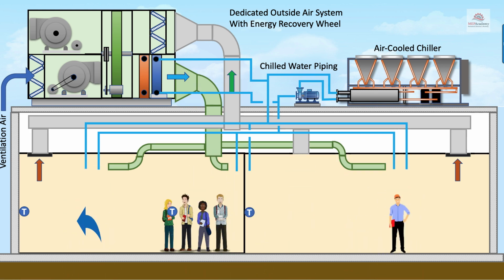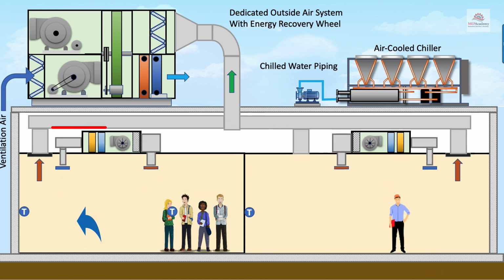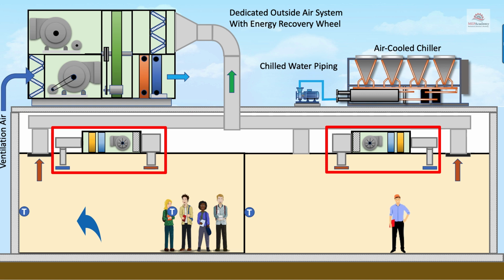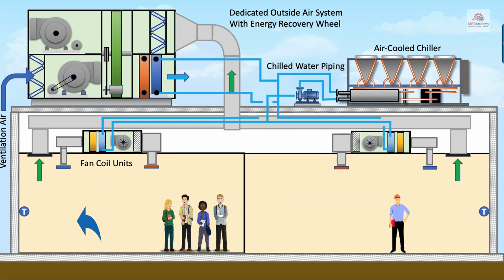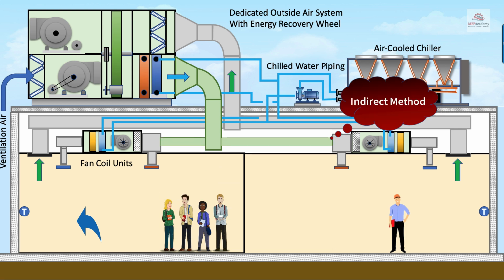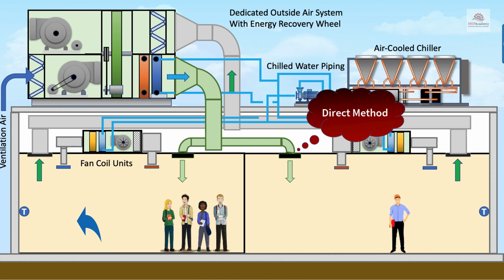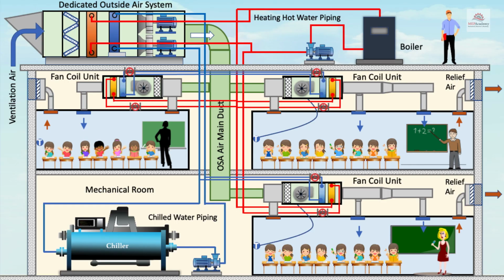Removing the chilled beams and redoing the ventilation duct and chilled water piping, we can install a couple of fan coil units with connection to the chilled water piping system as another option. The ventilation air from the DOAS unit is indirectly connected to the space by connecting it to the return air plenum on the fan coil. A supply grill can be installed on the ceiling to duct the ventilation air directly to the space. Using 4 pipe fan coils with a DOAS unit will separate the latent load from the sensible load. The DOAS will handle the latent load, while the fan coil units will handle the sensible load. The DOAS can deliver the supply air temperature low enough to pick up the additional room latent load also.